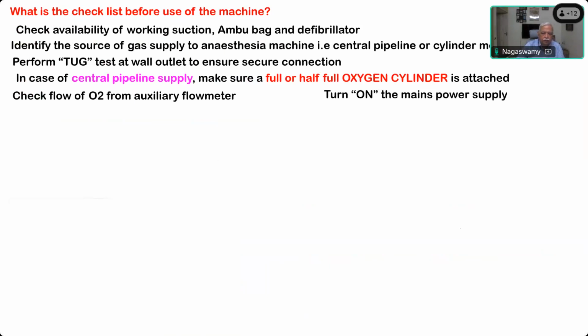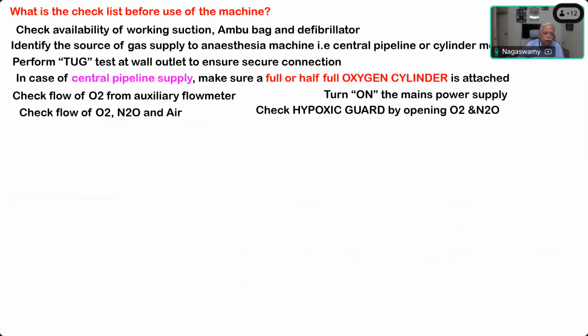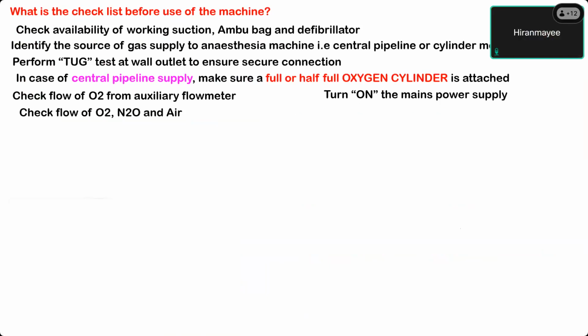Turn on the mains power supply. That is the next step. Check flow of oxygen, nitrous oxide and air. Check for hypoxic guard. How do you check for hypoxic guard? We open N2O and see if oxygen is also opening along with it in the flow meter. Is that the way to check for hypoxic guard?